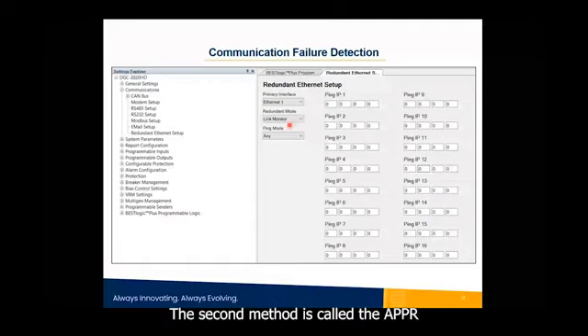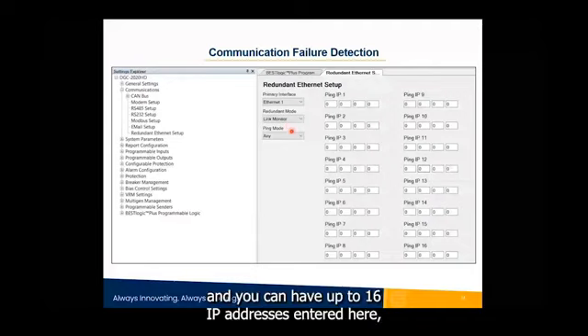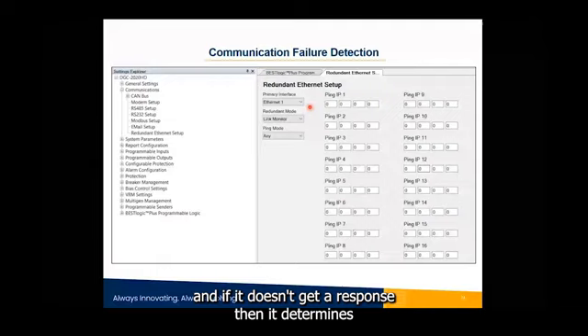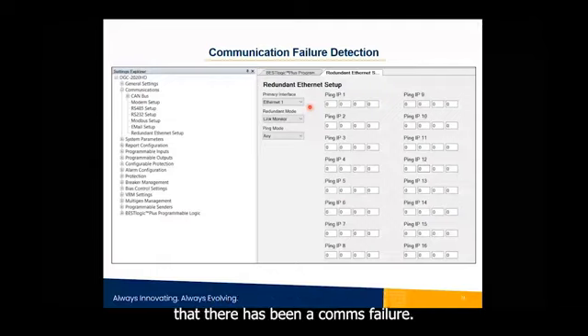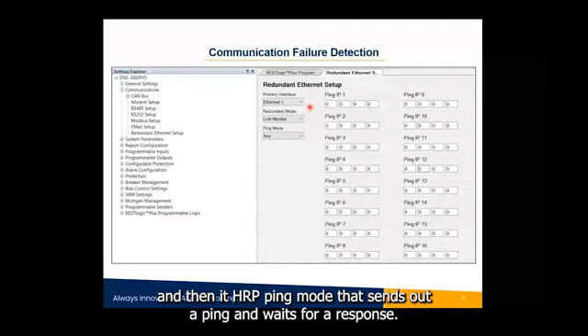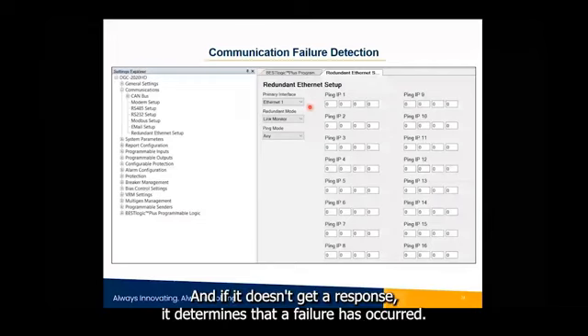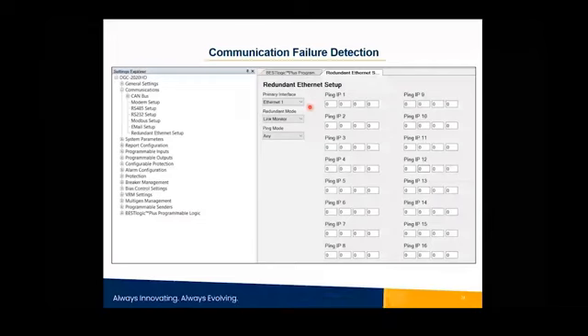The second method is called the ARP ping method. And you can have up to 16 IP addresses entered here, but the controller sends out a ping to the network. And if it doesn't get a response, then it determines that there has been a comms failure. So these are your two methods: the link monitor that just determines whether there's a broken link, and then the ARP ping mode that sends out a ping and waits for a response. And if it doesn't get a response, it determines that a failure has occurred.